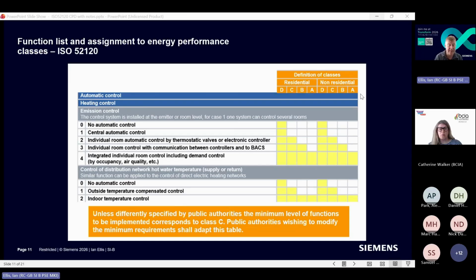And then the final option is again having the individual room control, but also having some sort of demand control or demand indication, whether that room is actually occupied, even though it might be during normal working hours. So let's say it's a conference room or a meeting room, it might not be being used the whole time. So some sort of feedback to say, no, there's no one in that space. Again, the BMS can then make a decision to start turning boilers down or turning them off, or if it's a multi-boiler system, maybe you don't need all 4 boilers or however many there are in there. So you can use that to design a system from day one.